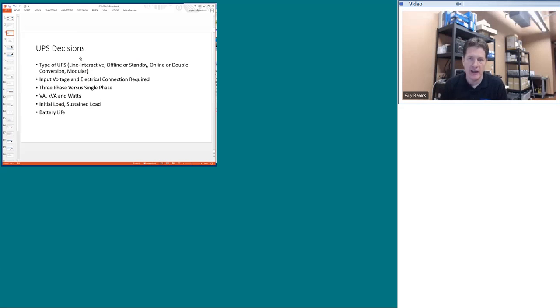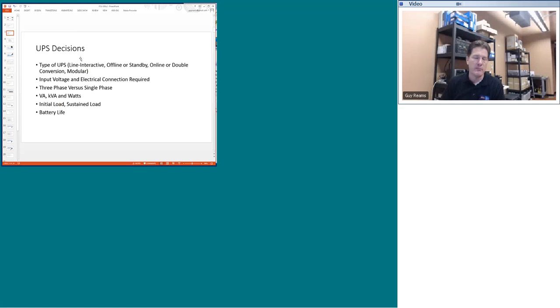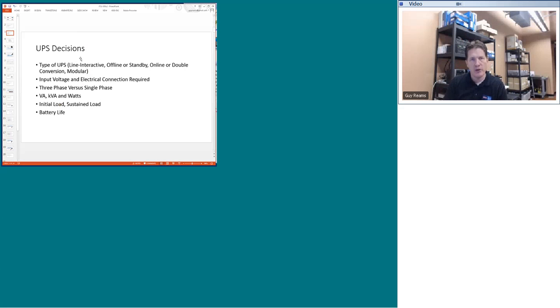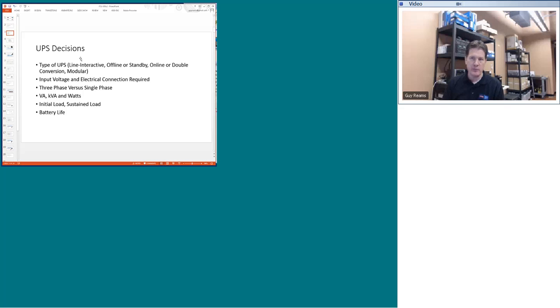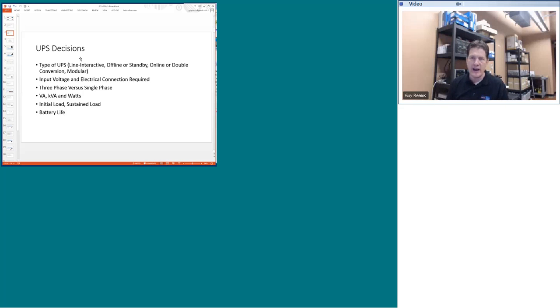The decision to buy a UPS requires a lot of thinking — it's not just 'go buy a UPS.' I'm going to narrow you down to two UPS types most common on physical security projects. The first decision is the type of UPS: do you need line-interactive, offline/standby, online double-conversion, or modular? Online double-conversion and modular UPSs are generally too high-end for physical security, so really it's a decision between line-interactive and standby UPSs.